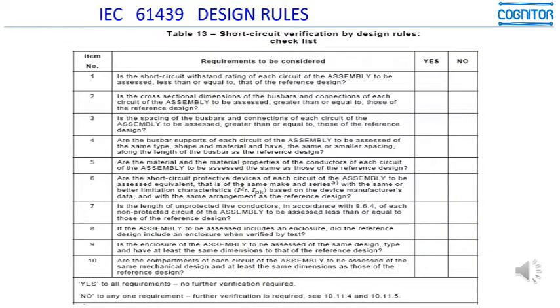In these 10 rules, if you say yes to all these requirements, no further verification is required. That is, you don't need to test anything more, or to calculate. It is as if the other equipment — the not-tested one — was fully tested.